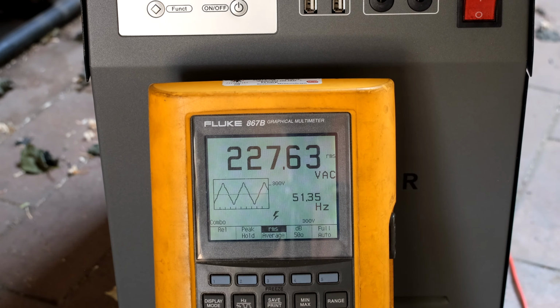Right, so the first thing we notice is that the output is no longer a pure sine wave, because it is bypassing the supply directly to the output. Remember that my meter is measuring the output of the inverter, so that graph you're seeing there is actually what is going to be fed to my loads. You can see that that graph has changed from a sine wave to a triangular type wave because the generator does not give a pure sine wave.